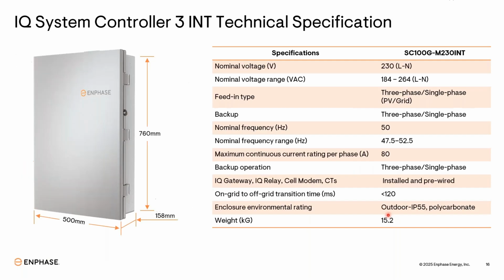Controller technical specifications: the nominal voltage is 230 volts, and the voltage range is 184 to 264 volts. The feed-in type supports both single phase and three phase. Backup also supports both single phase and three phase. Frequency is 50 hertz, and the range is 47.5 to 52.5. The maximum input current from the grid, it can sustain up to 80 amps per phase. Backup operation, as I said, is three phase and single phase both.